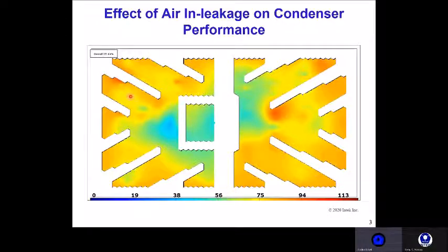This is a performance map developed by Intek that illustrates the tube bundle after it was fitted with hundreds of temperature sensors. Additional instrumentation was used to measure pressure and circulating water flow rate. These measurements are used to calculate cleanliness factor based on inlet temperature, condenser pressure, and circulating water flow rate. This is not computer modeling, but based on real-time direct measurements. The colors represent cleanliness factor calculated from these temperature sensors on the outlet of individual tubes.